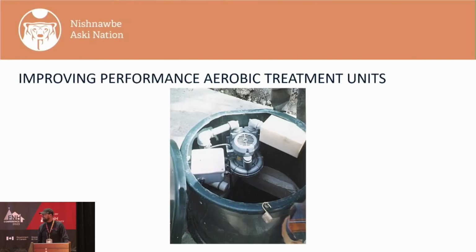So one of these ways is aerobic. I didn't talk too much about how a septic system is an anaerobic condition. It exists without oxygen. The bacteria in a septic system are anaerobic, or they don't use oxygen. To increase the treatment, we can put an aerobic unit after an anaerobic unit and get aerobic bacteria to do some additional chewing up of the stuff in the septic system effluent.